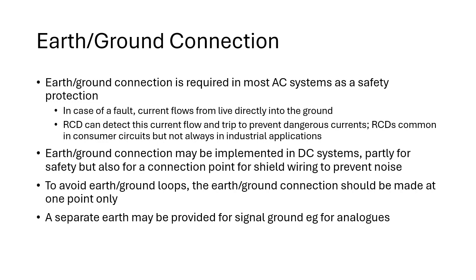So if we use an RCD, what could happen is we could end up tripping the system accidentally when we don't want to. So we often see RCDs in consumer circuits, but they may not always be present in industrial applications. And the other side of that is the amount of current we need to shunt down as well. An RCD might need to trip a very large amount of current, so it would need to be a very big, expensive device. So we may have those as large protection relays, or we may not, but certainly RCDs are common in these consumer circuits.